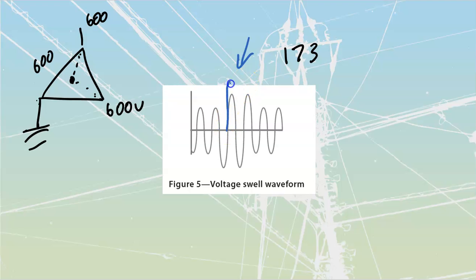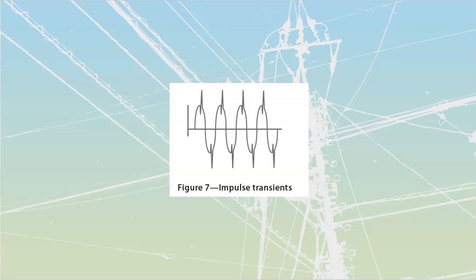This would be a voltage swell or surge. This would be a transient, where it spikes and then returns to its original waveform. The weirdness on the wave doesn't exist for at least that half cycle. If it exists for that half cycle, we call it a surge or swell. But if it lasts for less than half a cycle, we're dealing with what's called a transient. These are sudden peak events.